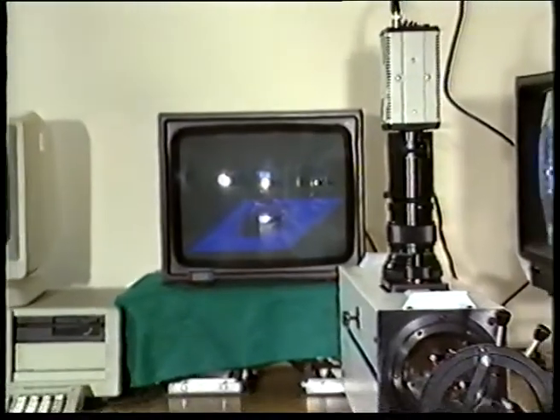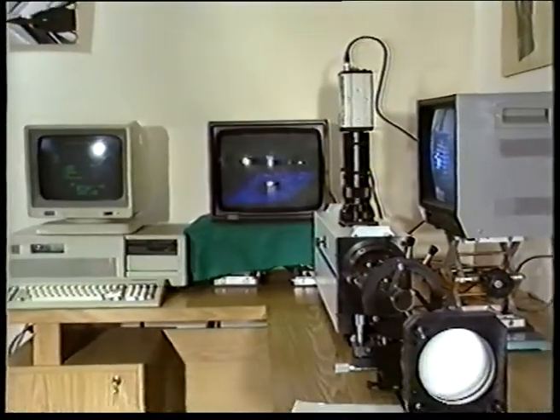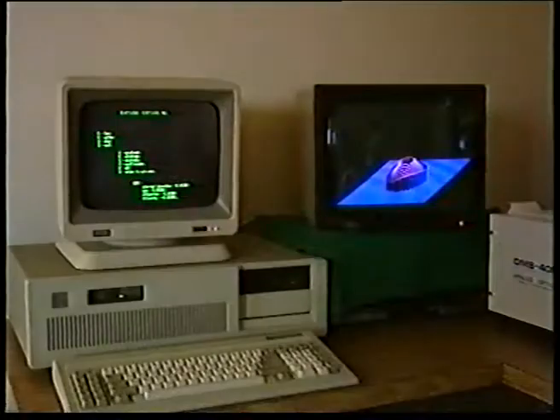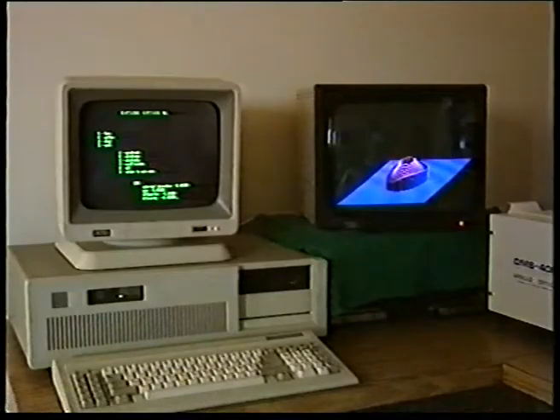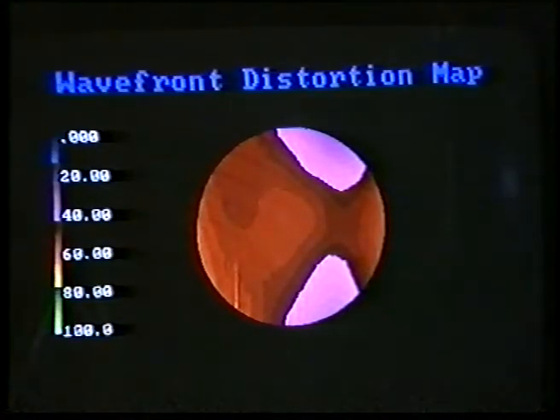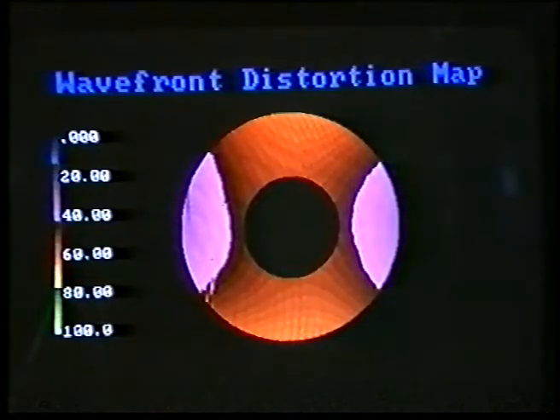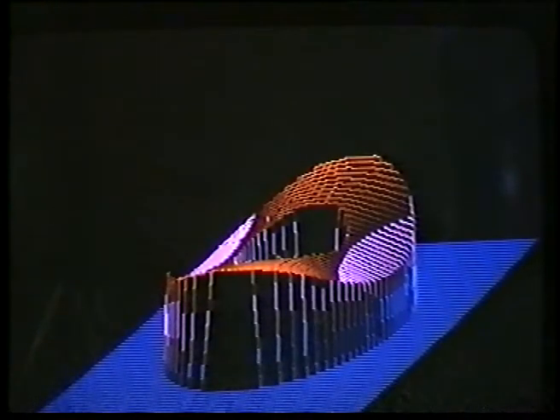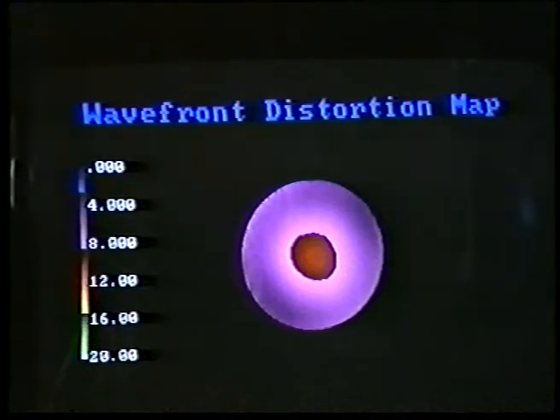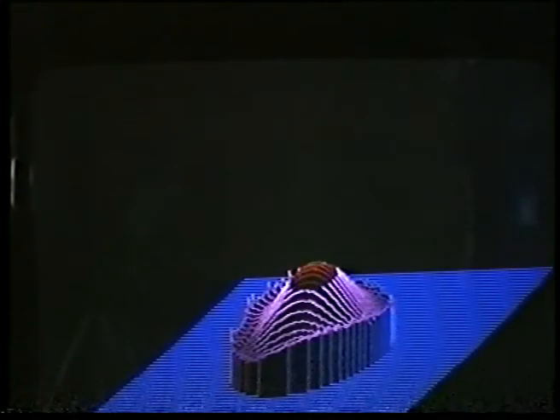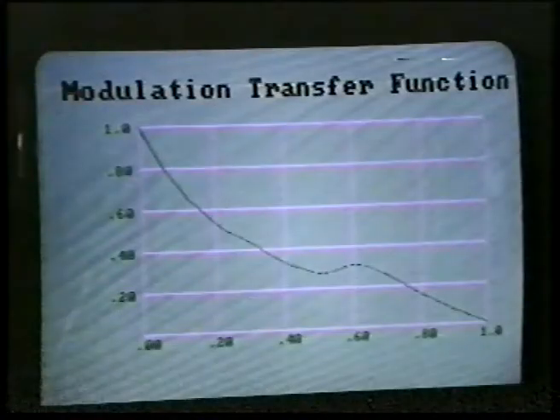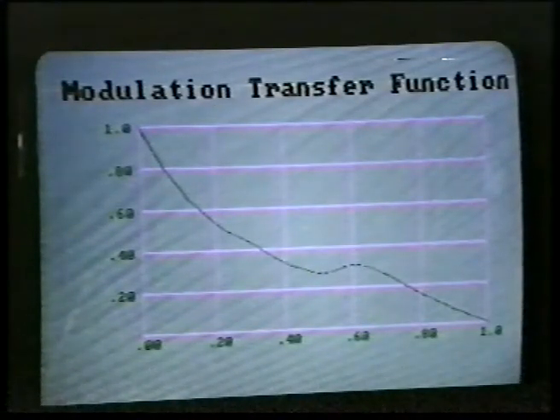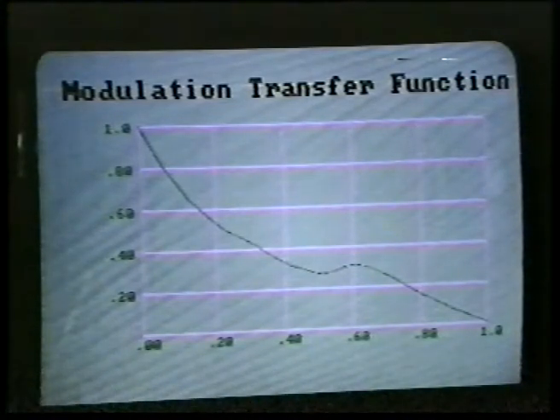More importantly, whichever application you are using, the OMS 400 can be connected to a computer to provide a complete analysis. Our unique IBM PC-AT based software provides a complete surface or phase mapping with lambda over 30 accuracy. On the computer, we see the surface topography of a silicon wafer with maximum height variation of 27 lambda. This 5.25 inch hard disk is another example of surface topography mapping. Our unique lens analysis system provides a wavefront distortion map, a complete fitted curve of all aberrations, values for the aberration coefficients, and an MTF curve. By changing the distance between the gratings, we can scan over the spatial frequencies and obtain an MTF curve of any optical component.